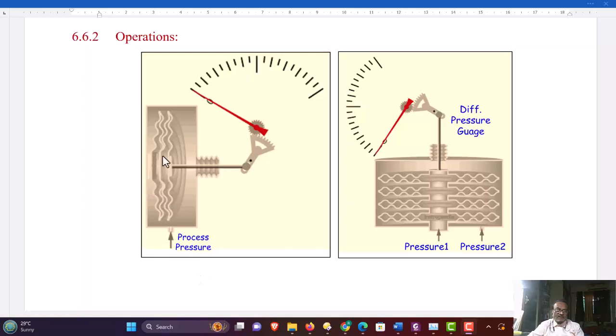See here in the first figure, the pressure is applied via the pressure port to the capsule. When pressure is increased, this capsule will expand, and due to that the rod connected to the capsule moves out. When this rod moves out, the mechanical gearing arrangement drives the gear train and moves the pointer on the scale. The pointer position on the scale indicates the pressure that is applied.